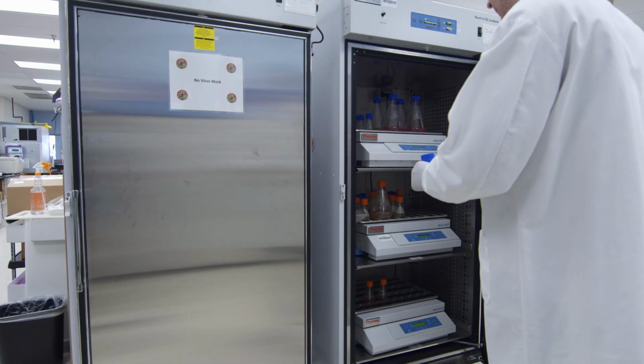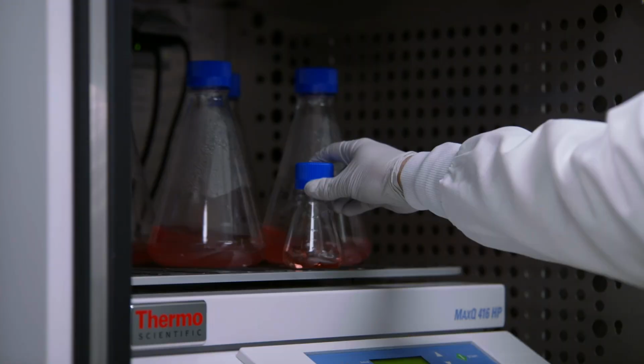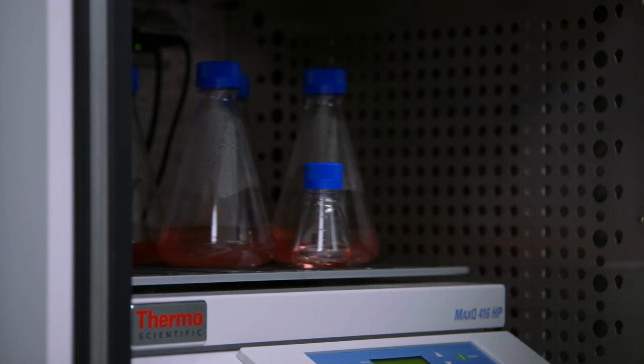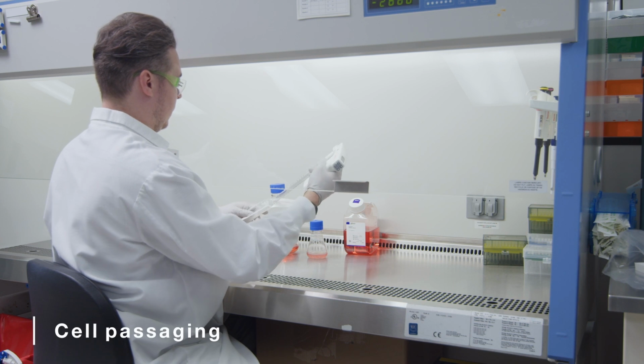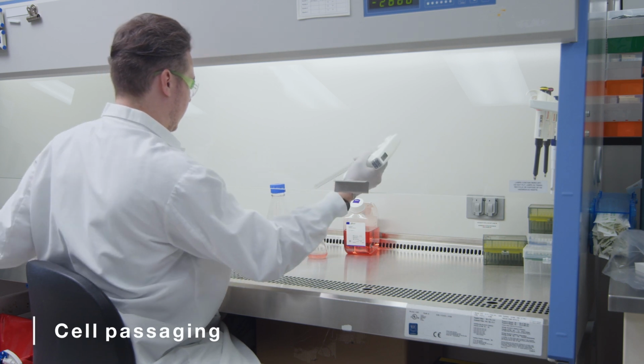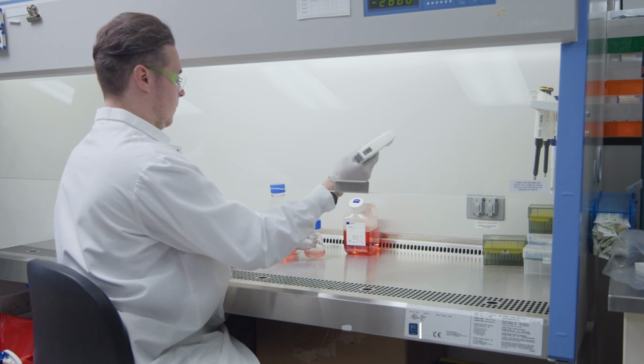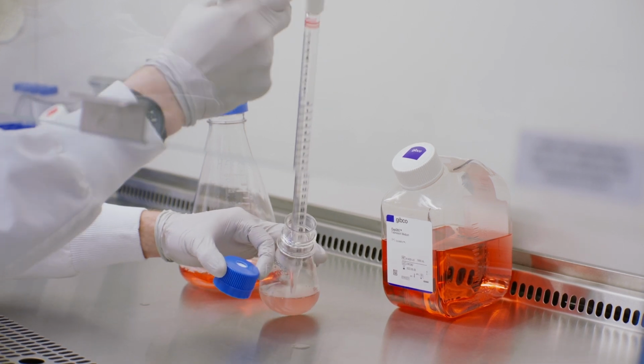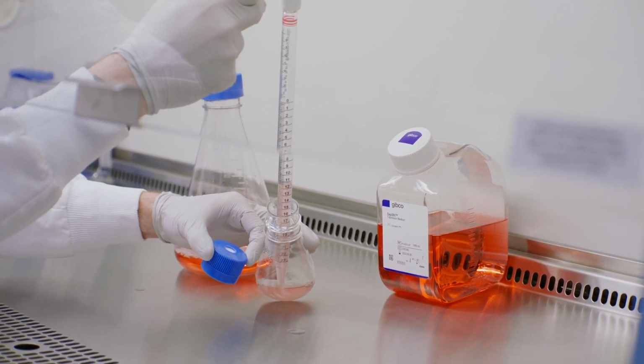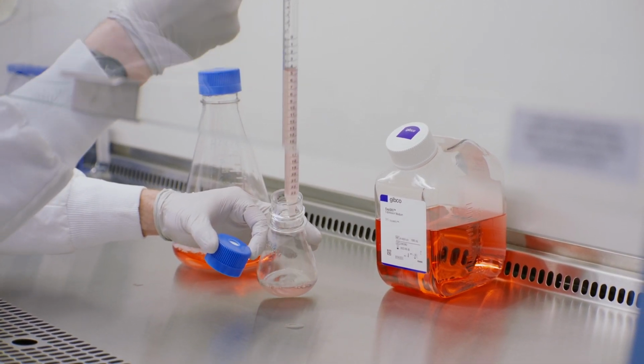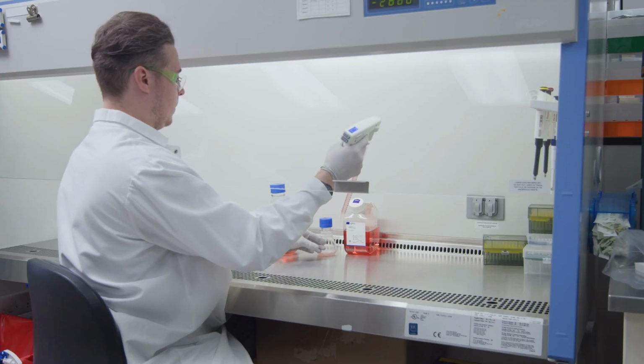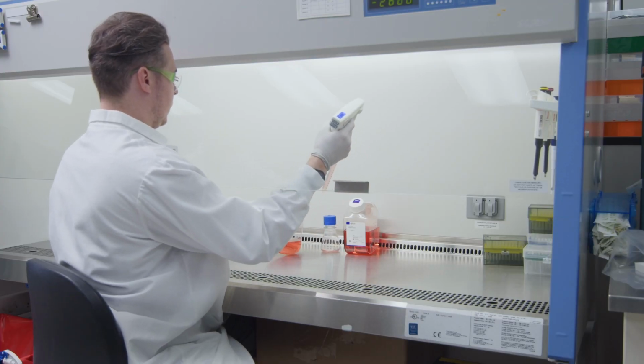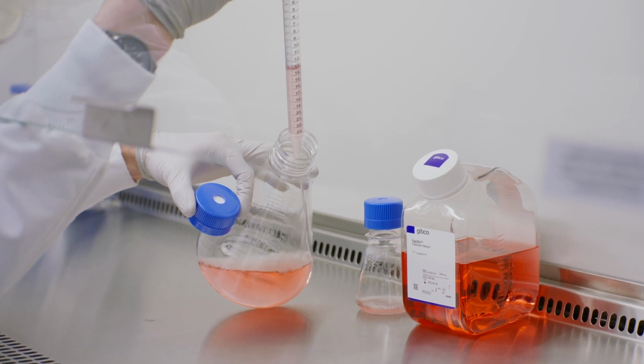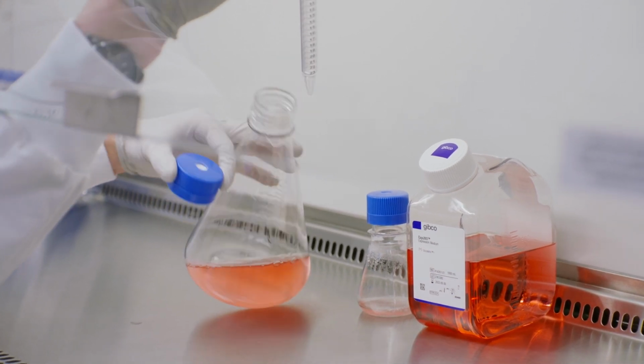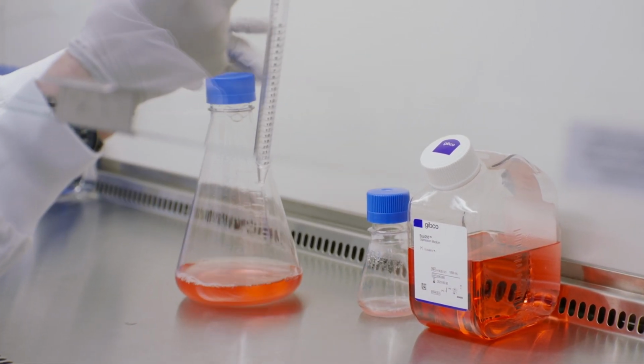Place the flask onto an orbital shaker in a CO2 incubator at 37°C with greater than 80% relative humidity. Perform the first subculture when cell viability is greater than or equal to 90% and viable cell density reaches greater than 1 million viable cells per milliliter, typically 3 to 4 days post-thaw. For routine cell culture maintenance, subculture cells upon reaching the specified viable cell density noted in the user manual. Repeat these steps to maintain and expand cells for banking.